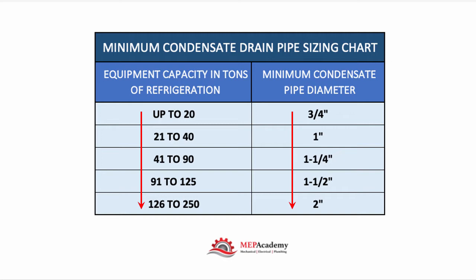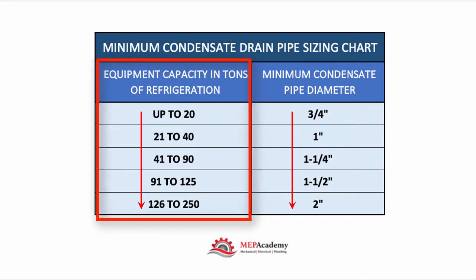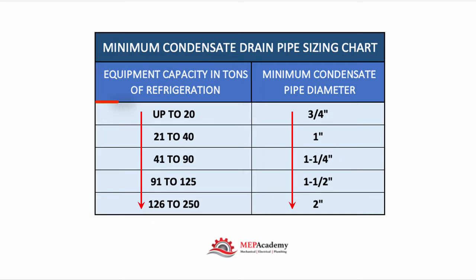Condensate drain pipe sizing is dictated by the local code. Enclosed you will find the requirements for many local codes, but be sure to check your local code for the requirements. If the outlet size of the equipment condensate drain is larger than what is shown in this chart, then you'll be required to use the larger outlet size. The chart is indicated by the tons of refrigeration — the air conditioning tons — so up to 20 tons you can use a three-quarter inch, 21 to 40 tons a one inch, and so on.